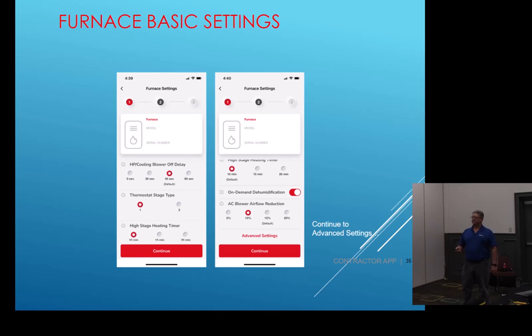Heat pump and cooling blower off delay. If there's anything that comes from the factory on this, it's set at 45 seconds. So when that compressor cuts off, that blower is going to run for 45 seconds. That's probably not a good idea in our climate with our humidity levels for that blower to run 45 seconds after that compressor is cut off. So you can come in here and select it to 0, okay? That way we're not re-moisturizing our house. In Vegas or up north, it might be a great idea. They want some humidity, but we don't want to dump any more back in the house after we've already taken it out, right? So that might be something you want to look at when you change one of these out, these 15, 16, or 18 SEER units.